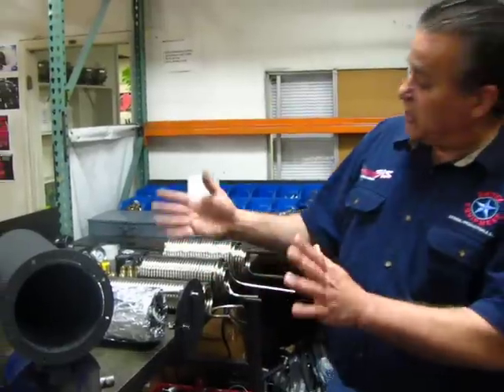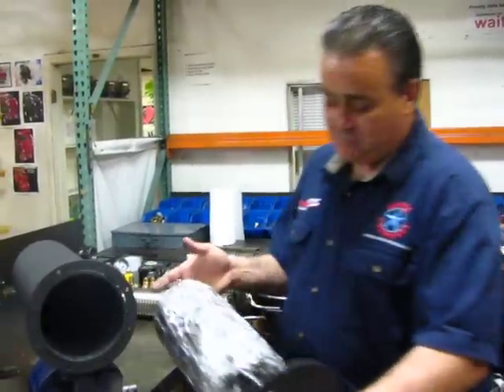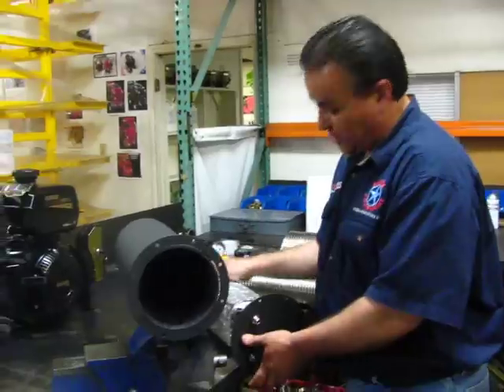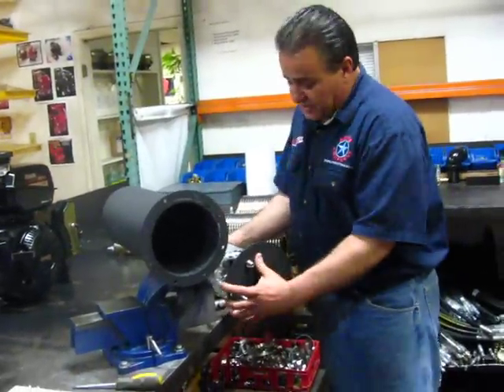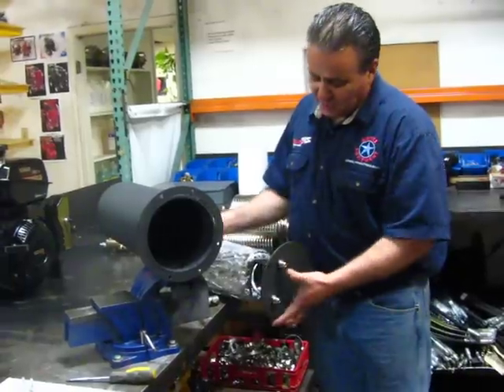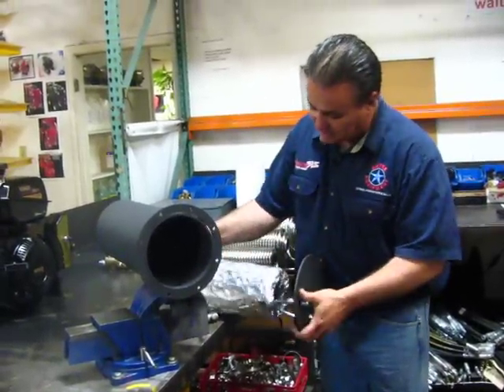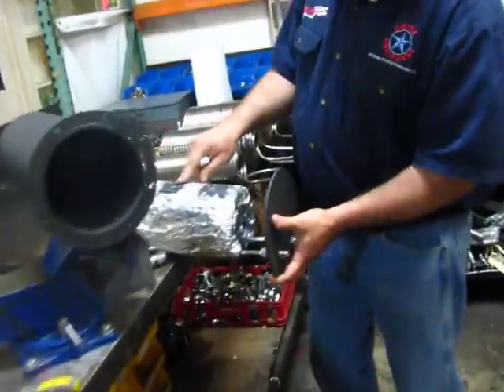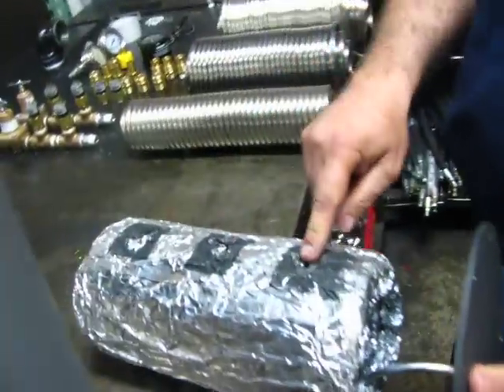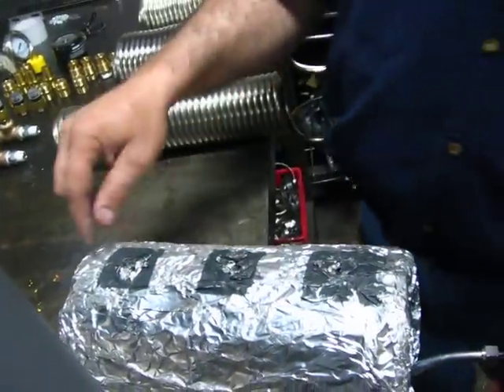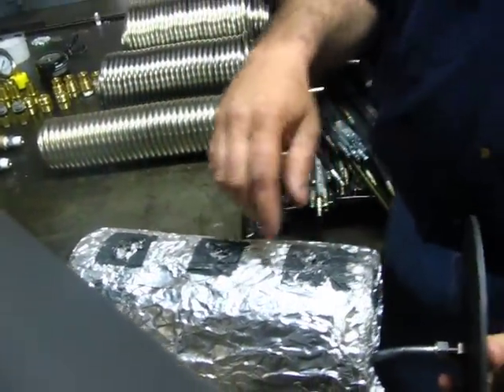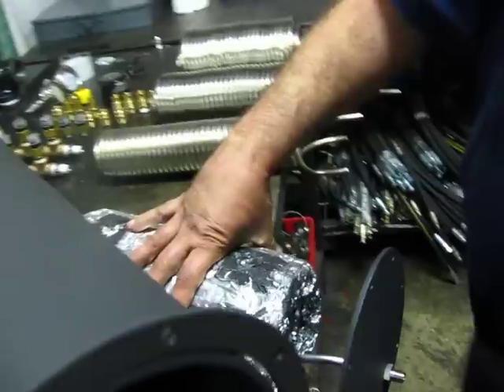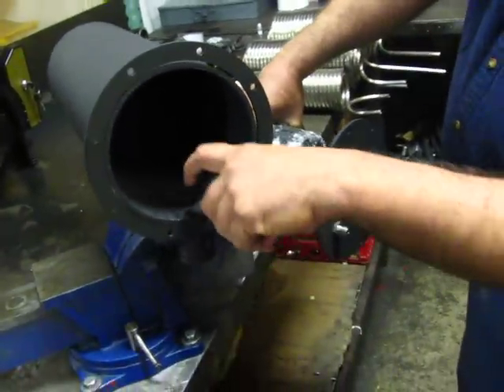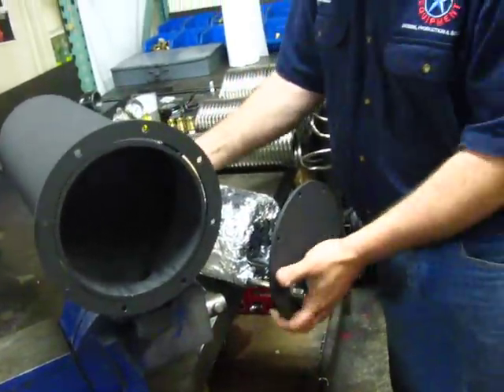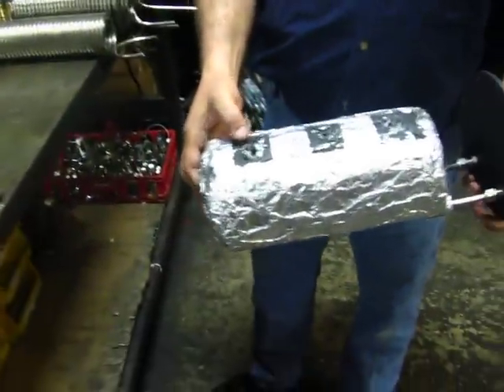Now let's say we already checked to see if our coil sits and is perfectly lined up. Every coil comes to you in one position, meaning at the bottom, if you notice, there's an area popped out for that condensation water, for it to be able to exit the coil, roll into the casing and get pumped out. So make sure your drainage is facing down.